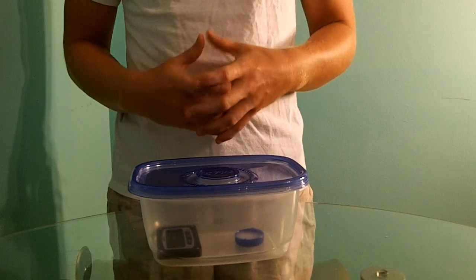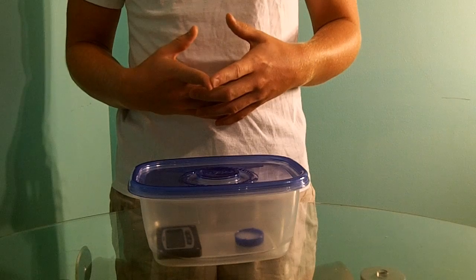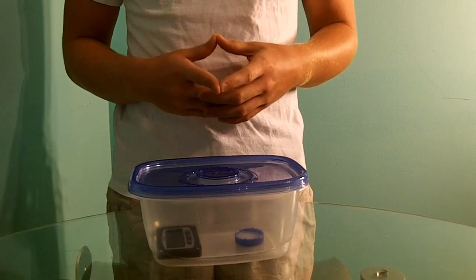And the reason we're going to want to wait this long is because it'll take this amount of time roughly for the salt to stabilize the humidity at 75%, which is what we're going to want. 24 hours later, if it's not quite on 75%, we're going to have to adjust. Ours is currently reading right around 71%.